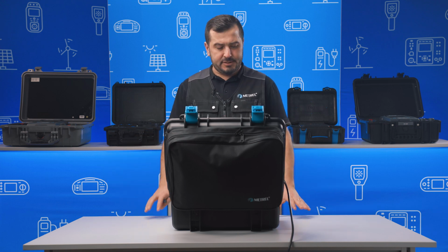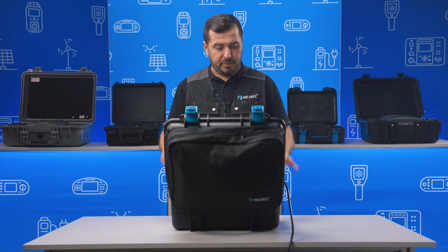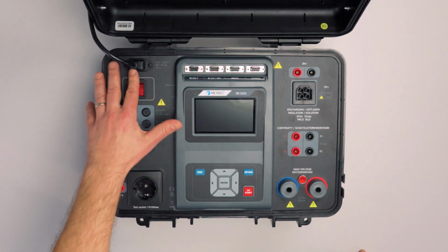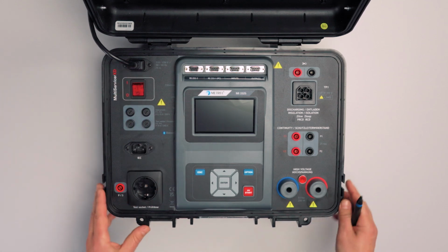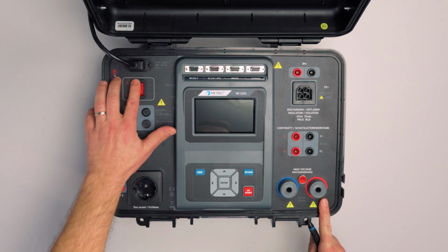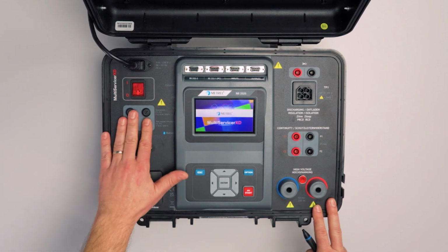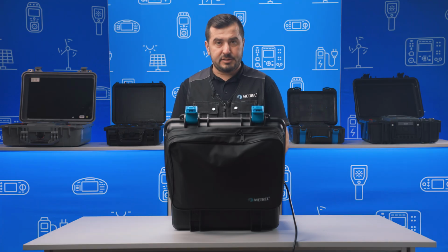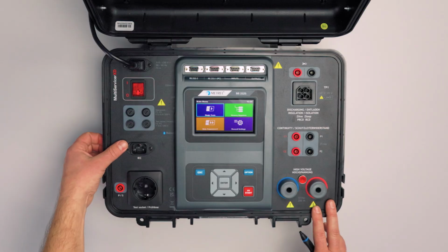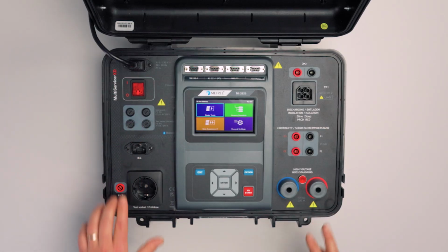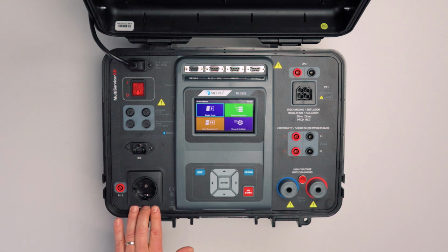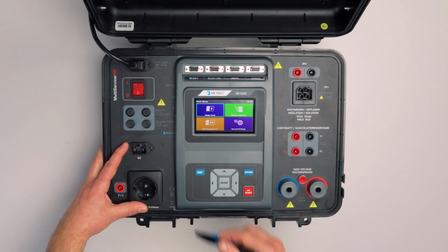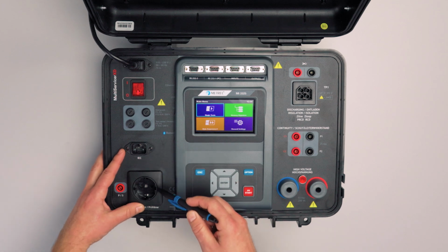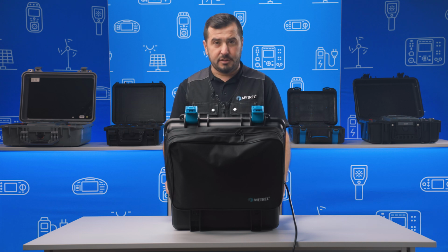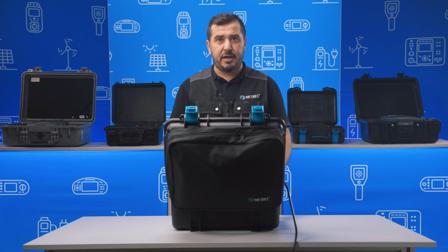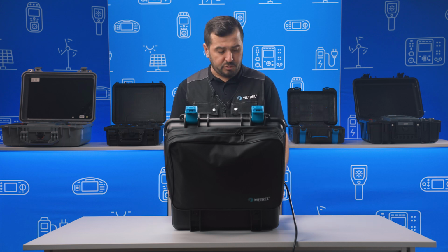Okay, so let us now focus on the description of the instrument's front panel. On the left top corner there is a port for supplying the test instrument. Below we have the on-off switch and the fuses, which are protecting the instrument supply circuit as well as the main test socket. After the fuses is the location of the IEC connector and also, as I said, the instrument's main test socket. Now, the IEC connector and the instrument main test socket can be used for testing different extension leads, PAT test leads, and also leads that may be RCD protected.